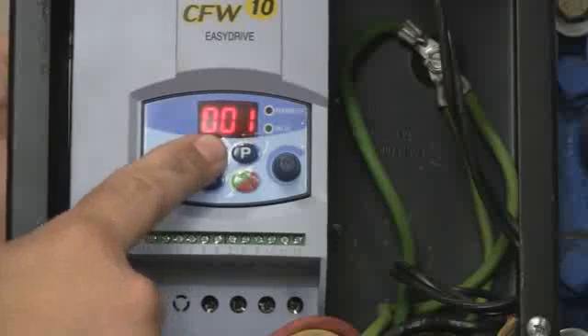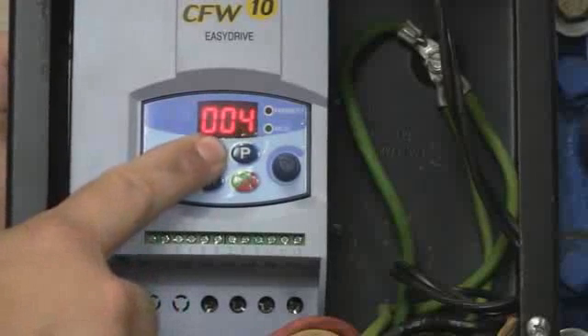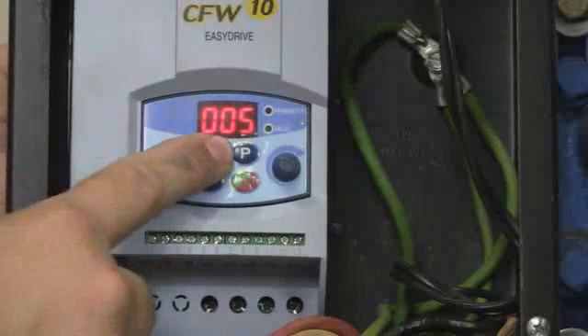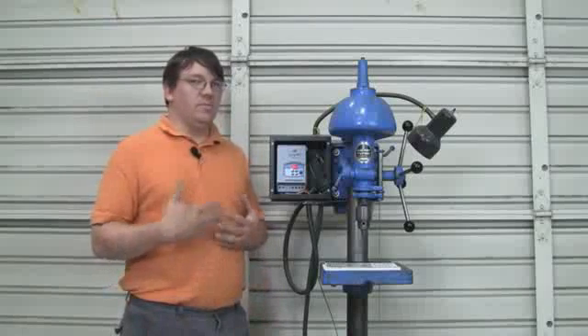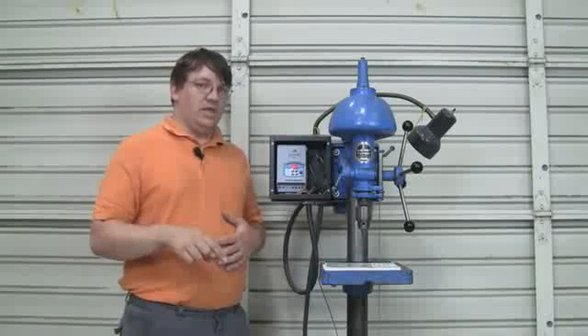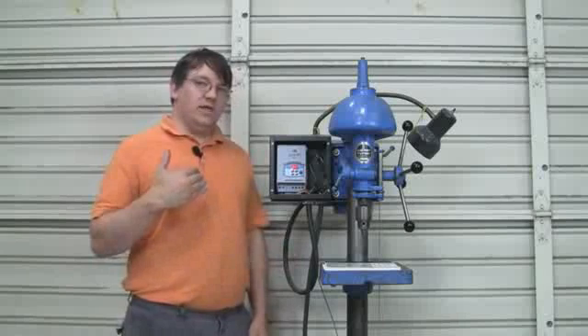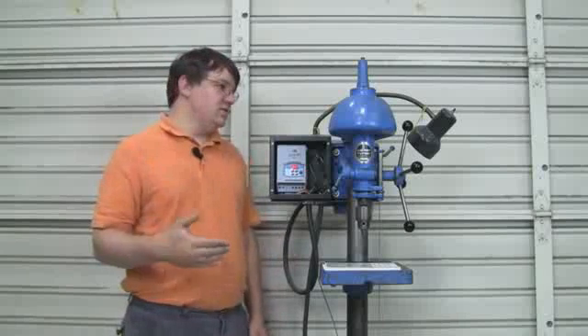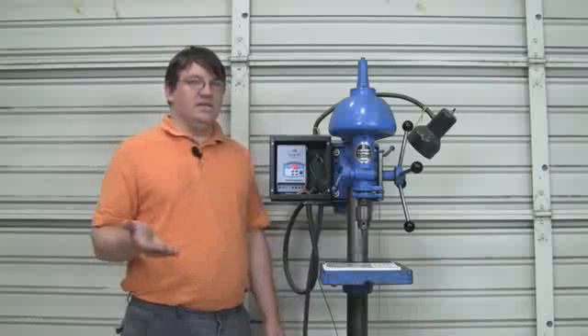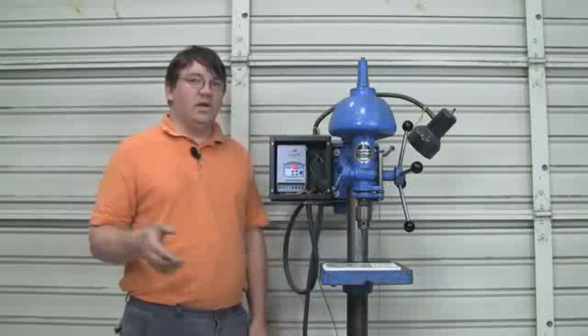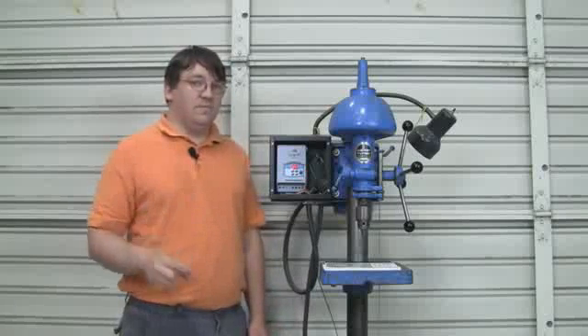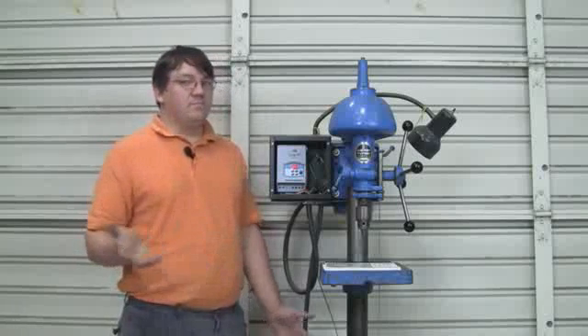The value layer is underneath that. When you press program, you switch to the value layer. This is the value you're setting that parameter to. For example, with motor speed, if I go into that parameter and hit program, it'll show me the default speed. I can then set what my motor speed is. If I have a 1700 RPM motor, I can set 1700 RPM, press program again to save it, and you're done.